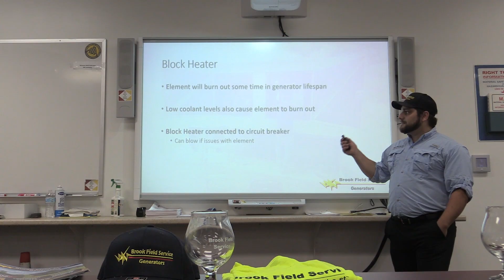The block heater is another significant issue Josh runs into all the time, especially on these larger systems. Your element's going to burn out at some point in the generator's lifespan. Low coolant levels are also a huge cause for the element to burn out, so make sure you're running at proper coolant levels - overfilled is always better than underfilled. The block heater is connected to the circuit breaker, which can blow if you have issues with the element and the block heater.